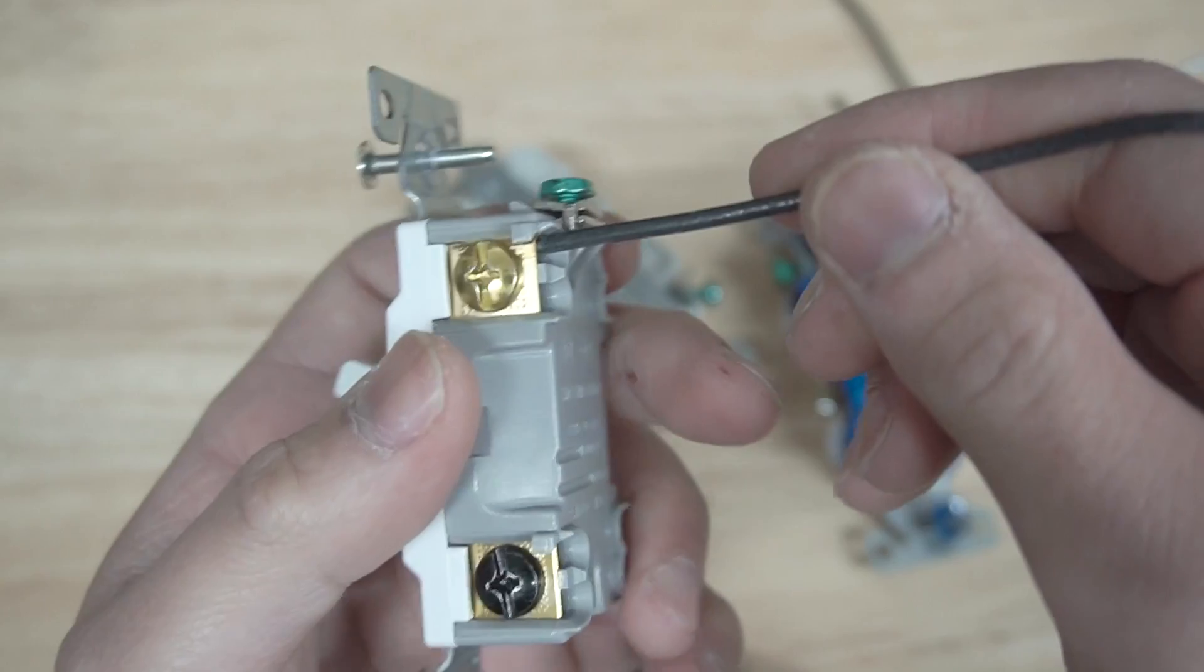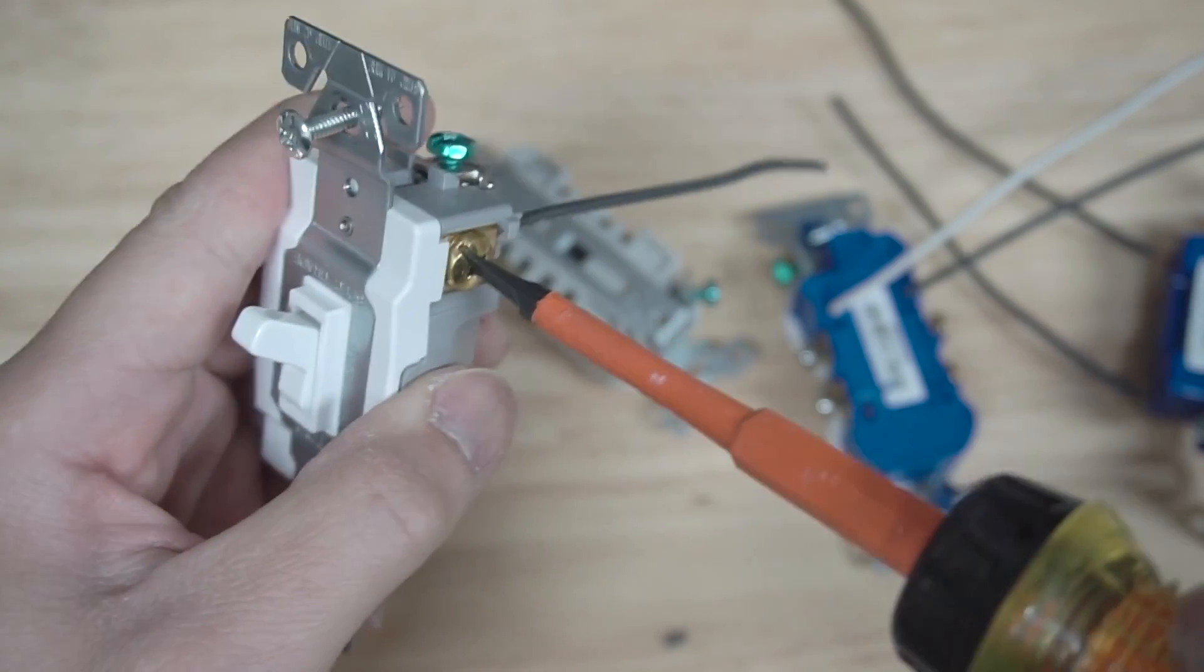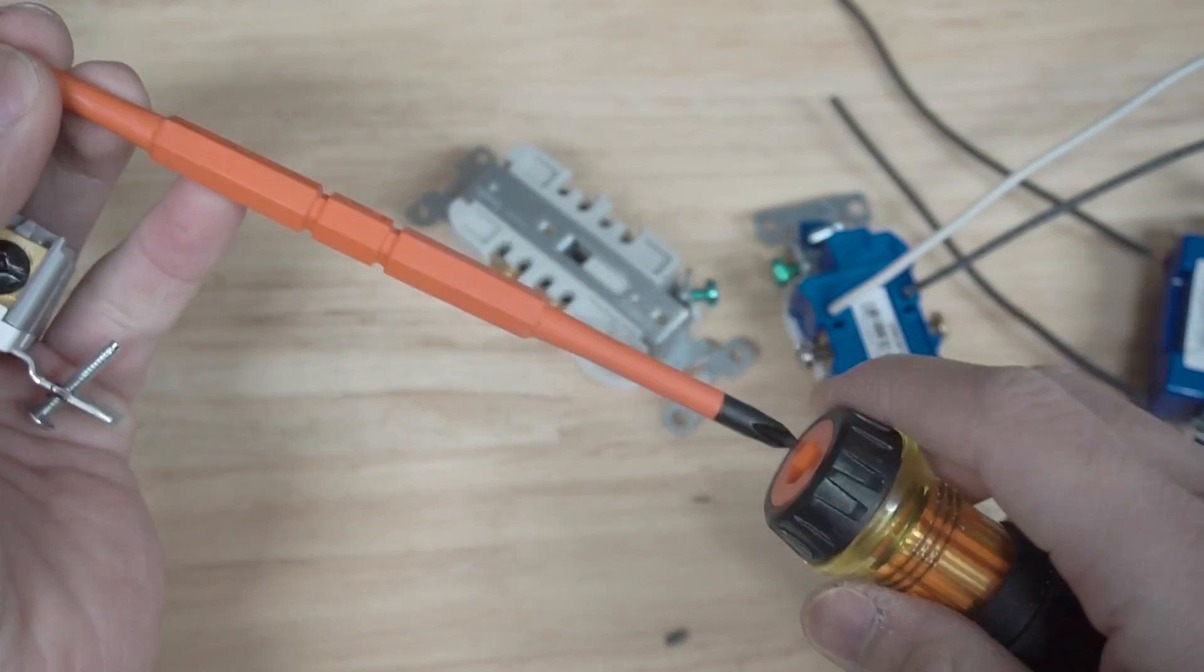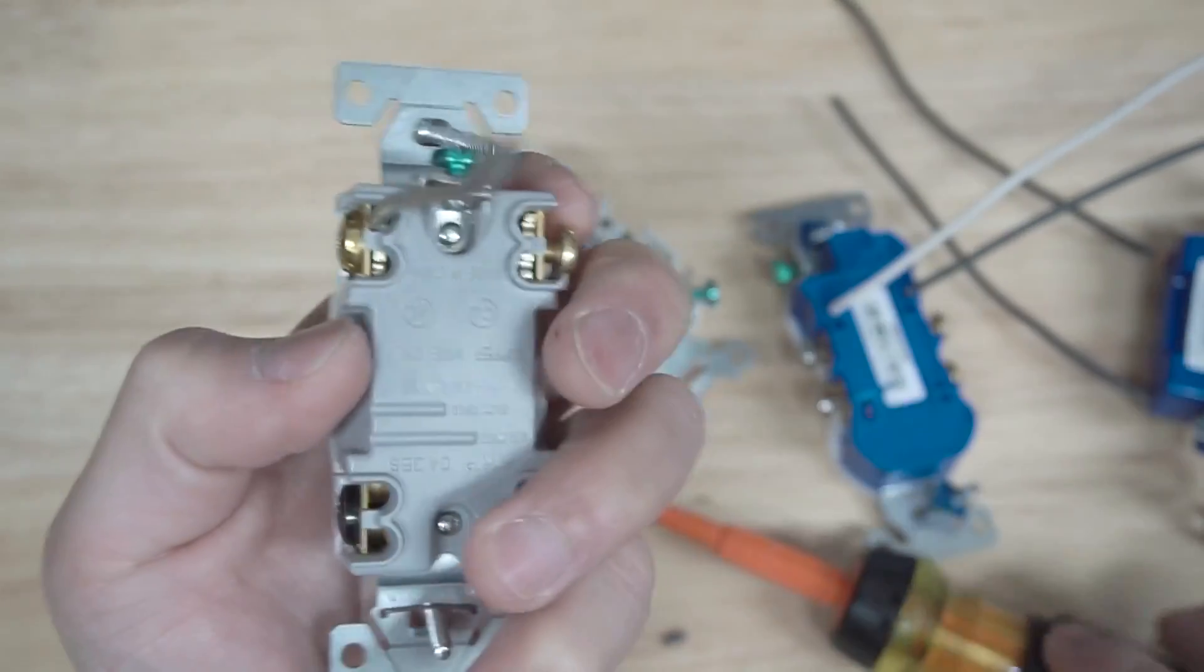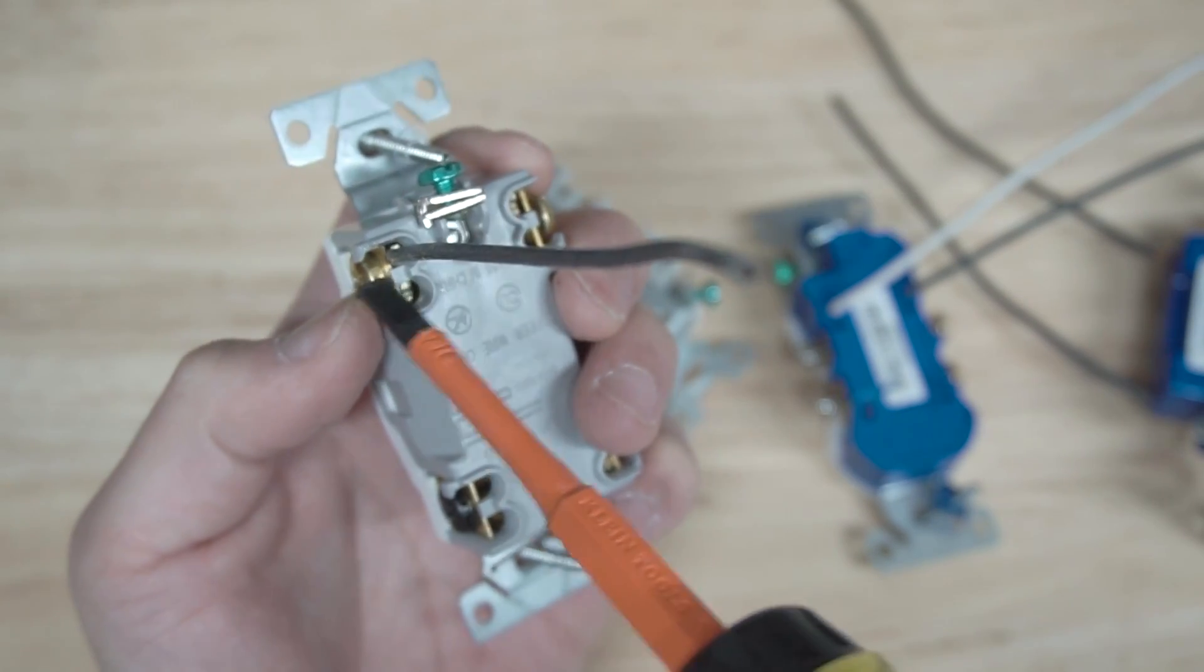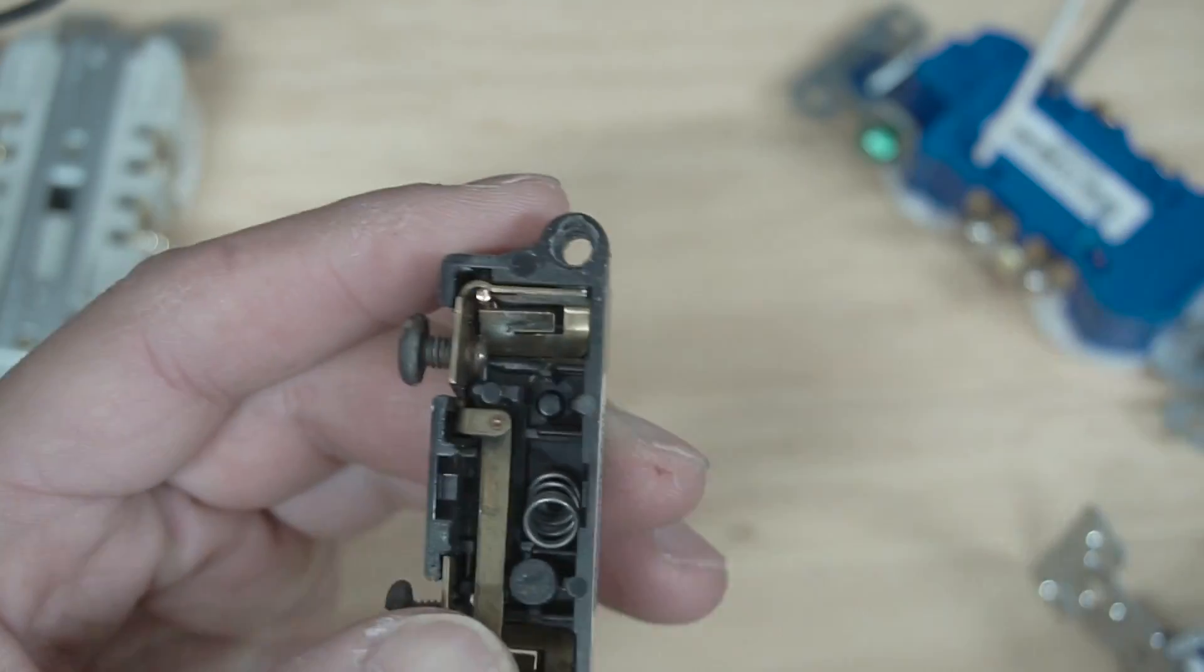Back wiring is fairly easy to do. If you put it right through here, clamp it down, back wire has enough clamping force. Notice how tight you can get this—you can tighten as hard as you can with your insulated screwdriver. It has a lot of clamping force onto it. Notice how the contact points and terminals are squeezed and sandwiched between the terminal plate right here and the back area as well. So you have two points of contact, almost surrounded and wrapped around this wire. You can probably say it's 80 to 90 percent in contact right here, all around the wire itself.